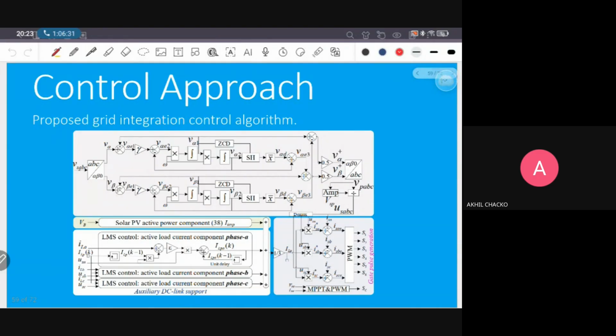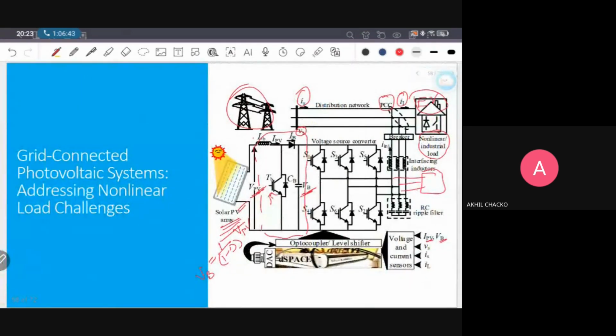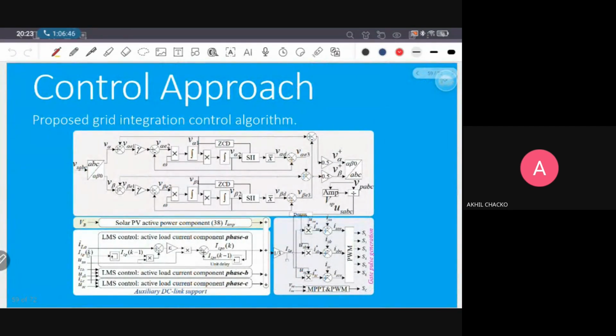So here, on one side, I am expecting voltage harmonics or voltage fluctuations. Even if I say this is an infinite voltage bus, I should be ready with withstanding all voltage fluctuations. So for safety purposes, I have measured or sensed three-phase grid voltages Vs A, B, C, and I have the DC link voltage VB. I have load current ILA, like that. And these all are the voltage processing loop. This is the current processing loop.